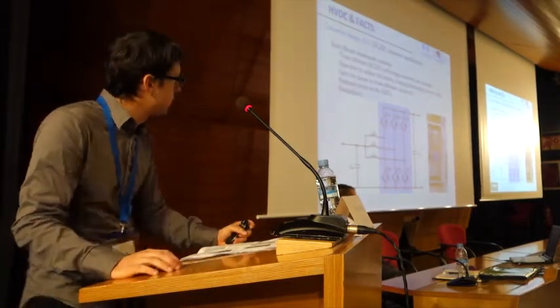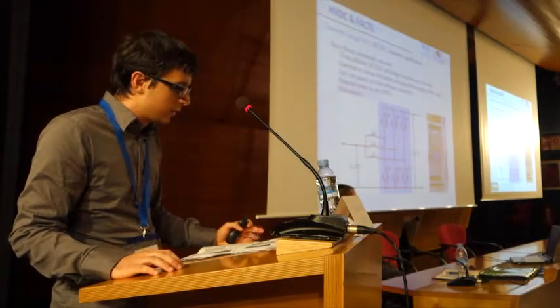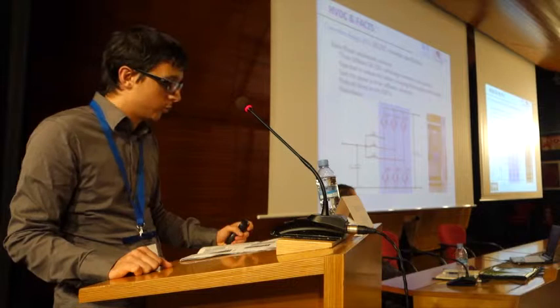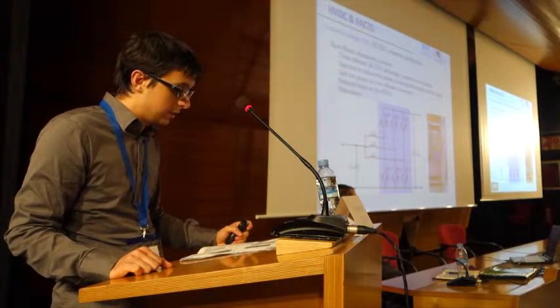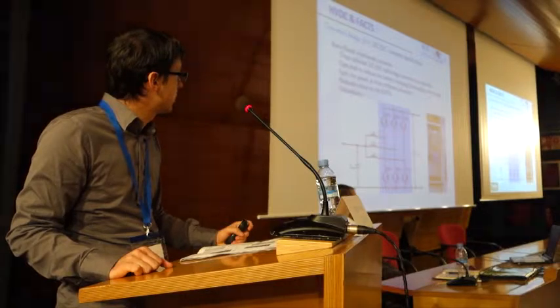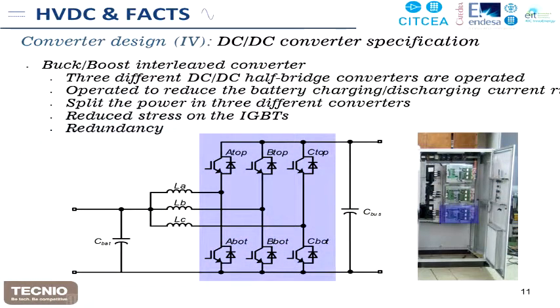If we look a little bit more inside the converter, for the DC-DC converter specification, we have decided to propose a buck-boost interleaved converter, in this case using 3 legs. So this means that we can split the power between these 3 legs, shifting the current signals 120 degrees between each one. And splitting the power, we can reduce the stress on the IGBTs and also give some redundancy to the system, because if we lose one of the legs, the system can continue operating in a degraded mode, obviously injecting or consuming more ripple to the energy storage system, but at least without stopping the operation of the system.